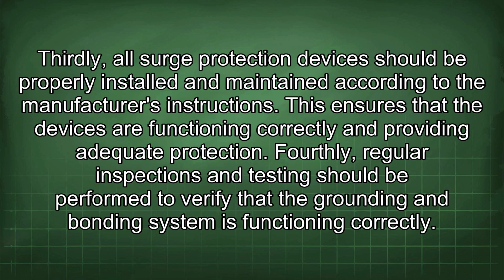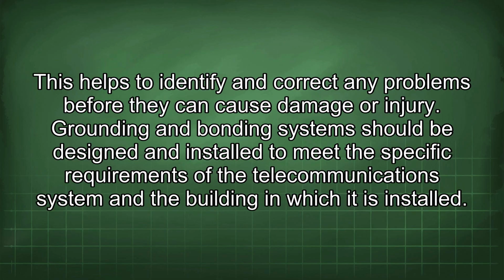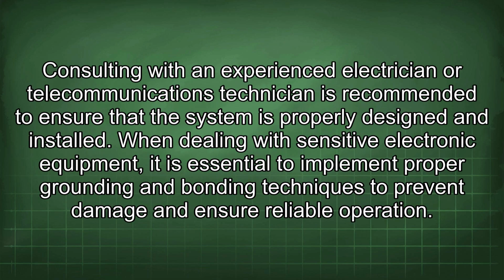Thirdly, all surge protection devices should be properly installed and maintained according to the manufacturer's instructions. This ensures that the devices are functioning correctly and providing adequate protection. Fourthly, regular inspections and testing should be performed to verify that the grounding and bonding system is functioning correctly. This helps to identify and correct any problems before they can cause damage or injury. Grounding and bonding systems should be designed and installed to meet the specific requirements of the telecommunications system and the building in which it is installed. Consulting with an experienced electrician or telecommunications technician is recommended to ensure that the system is properly designed and installed.